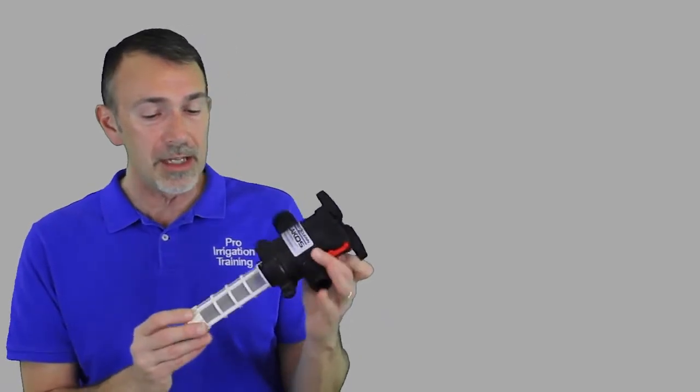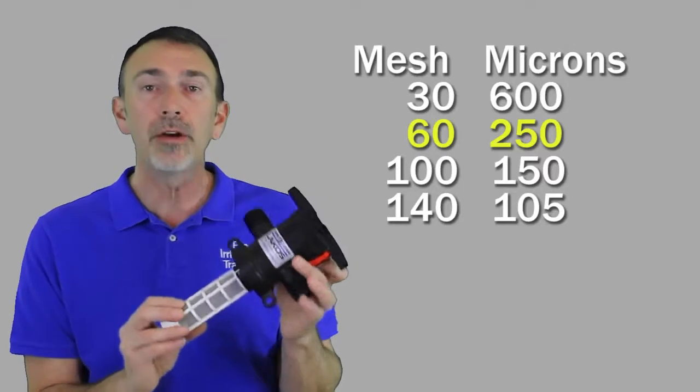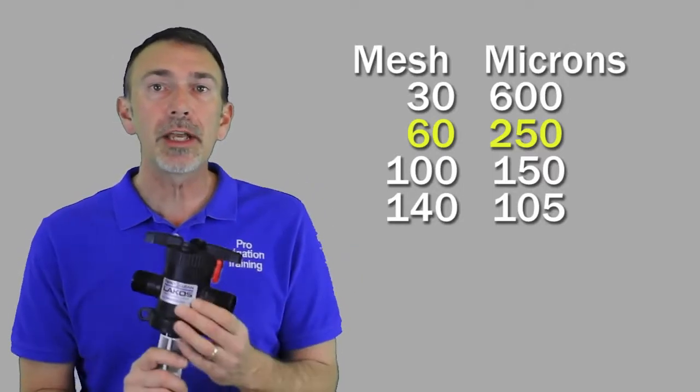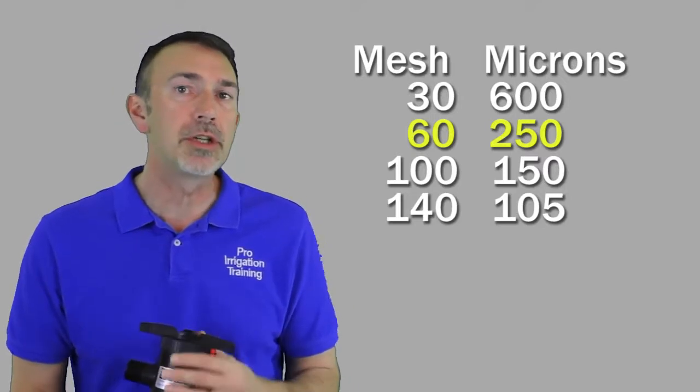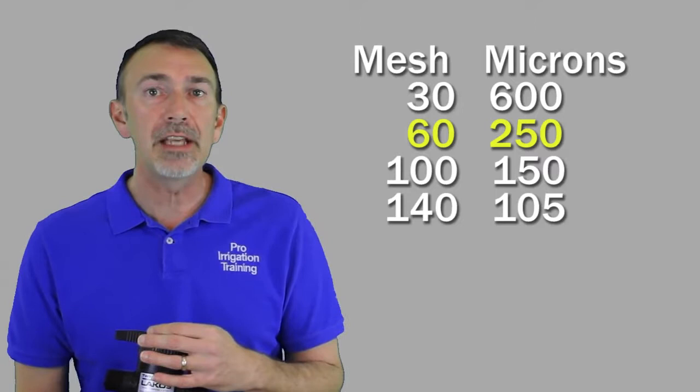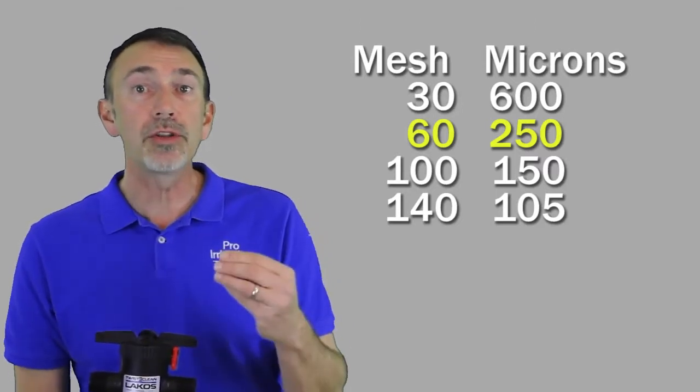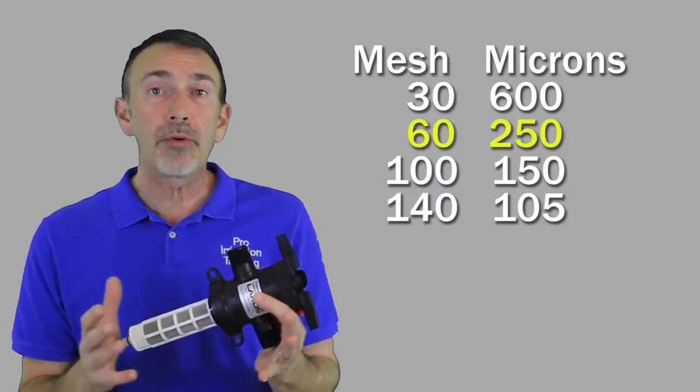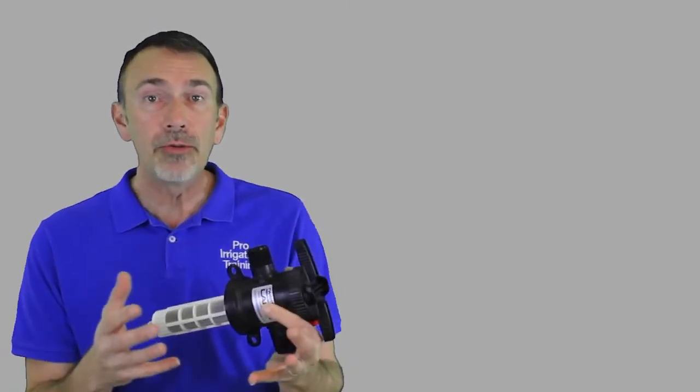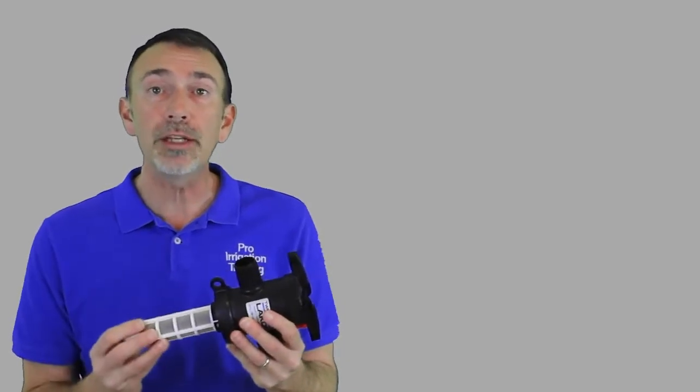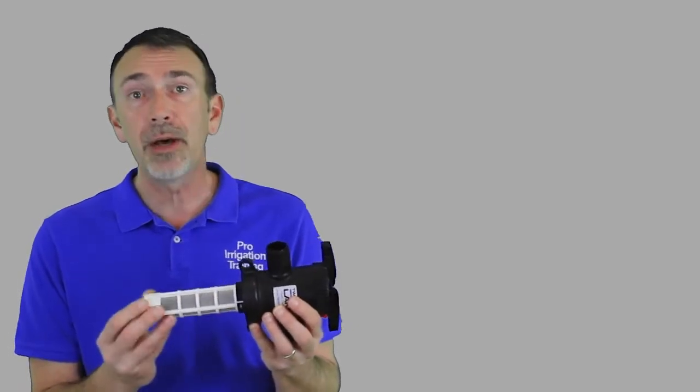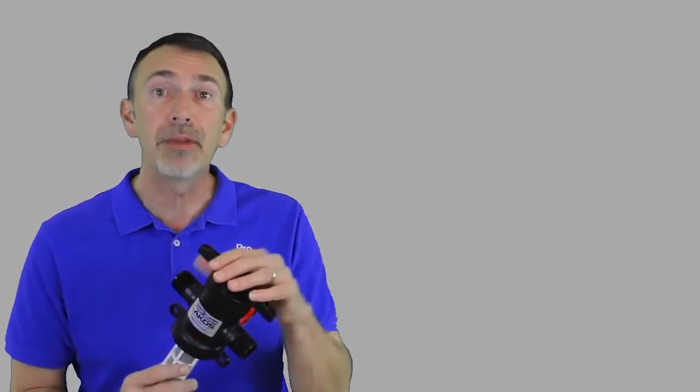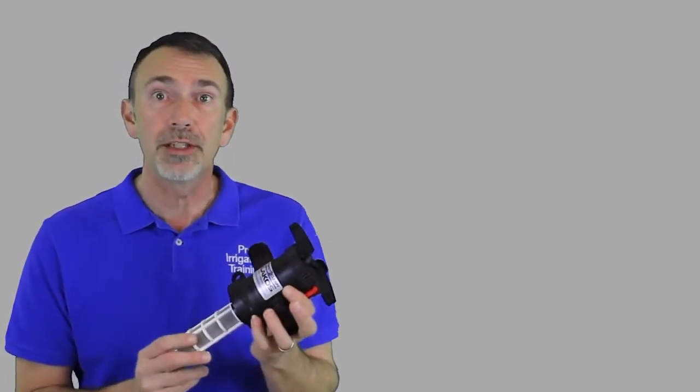So let's talk about what we're looking at here. And what you have here is this is a 60 mesh that comes with this at 250 microns. So let's take a look here at a chart because you have a few different options that can come with this. And as you see from this chart, as the mesh size increases, the particle size that can make it through the screen decreases. So if you're having problems with this and you're not getting enough flow through it or if it gets clogged too quickly or just screens out more than you want it to, then you can get one of the optional screens, larger or smaller size, and put it on there and adjust this down to where you want it. Some of the ones that I've shown previously don't have the optional screens that you can buy, but this particular one does.